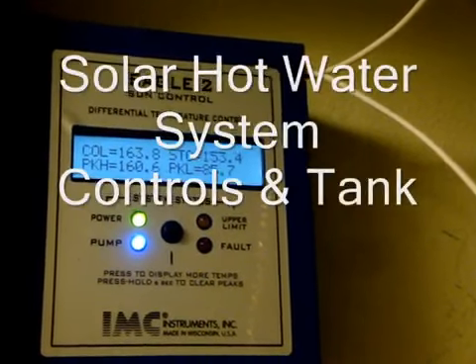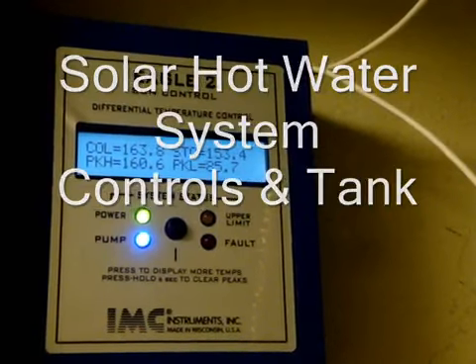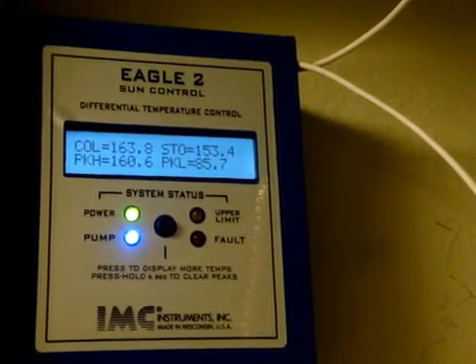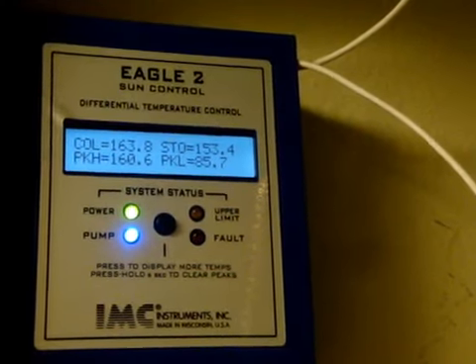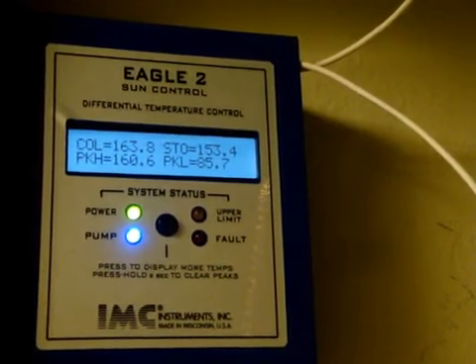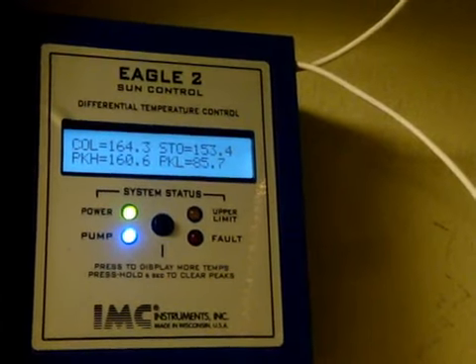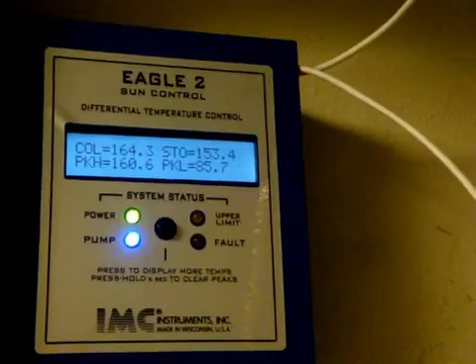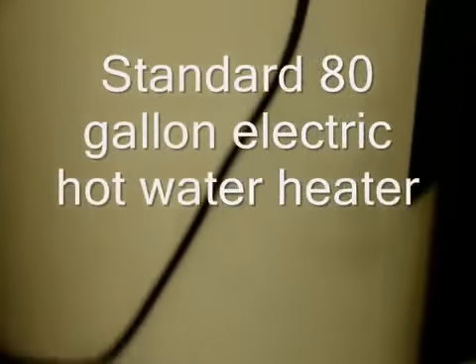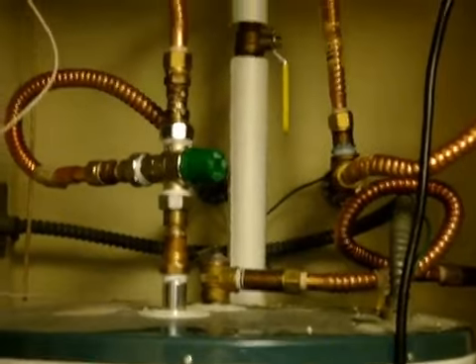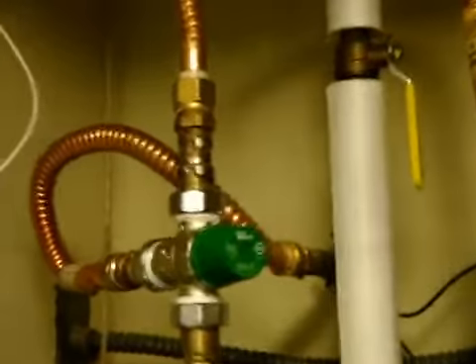Okay, you're looking at the controller for the solar hot water heater. The collector up on the roof has 163 degrees in it right now, and the storage tank has 153 degrees in it. The storage tank is simply a standard electric 80-gallon hot water heater. I keep the breaker to that turned off. I don't have any issues at all, unless I have an extremely heavy use day where a whole bunch of people are over.